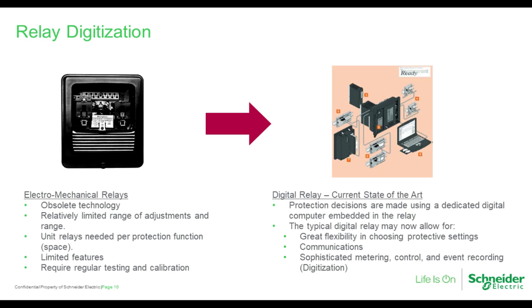Relay digitization. Many of us have already seen a lot of these old electromechanical relays out there. They're obsolete. The technology is obsolete. The range of protection is rather short for each particular relay, and there's a limited adjustment in that. Unit relays need, per protection function, the space. We used to have, for 50-51 protection, one relay per phase, including 3 on the door and then additional relays. Now we can bring it down to a digital relay, current state of the art, and protection. Newer relays incorporate more protection and more communication capabilities. New relays are also compliant to IEC 61850, which in many facilities is a protocol that is required.